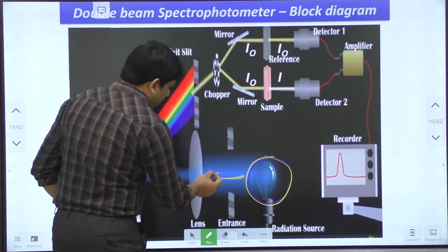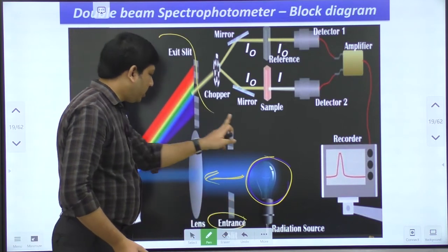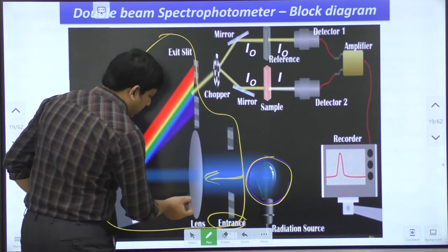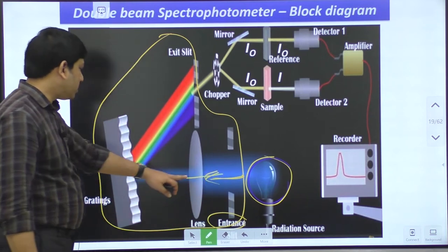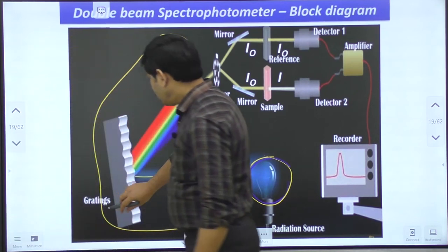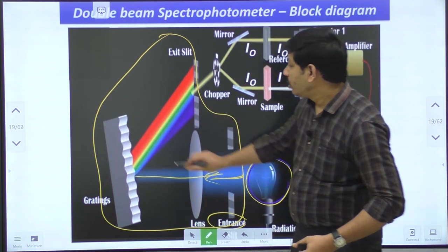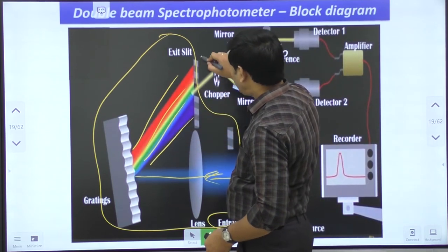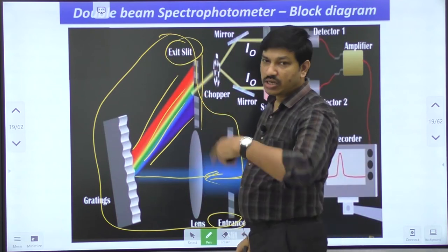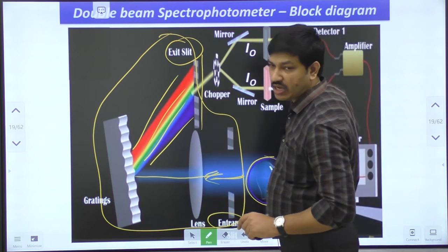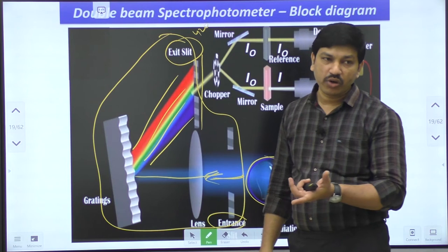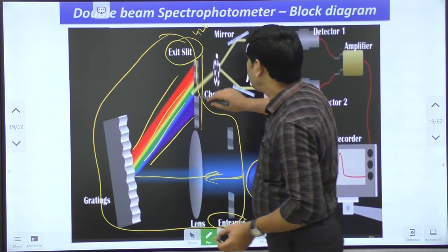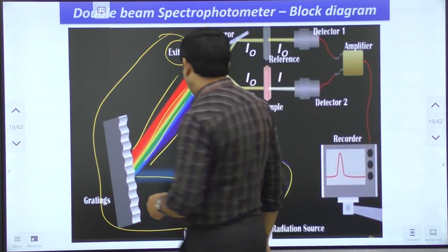The radiation then enters the monochromator. The light first enters a lens, and due to the lens, the radiation goes to a grating surface. The grating divides the light into different wavelengths. All the radiation then passes to the exit slit, which allows only the required wavelength to pass through toward the sample. For example, if we set it to 420 nm, only 420 nm radiation is allowed through to the unknown sample.